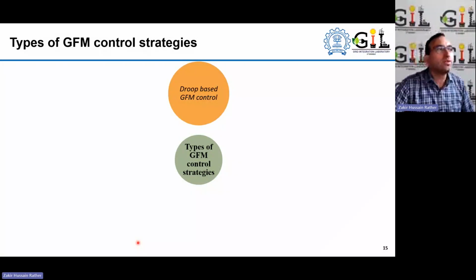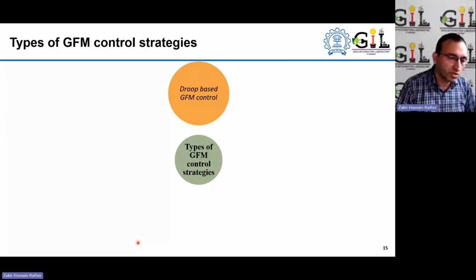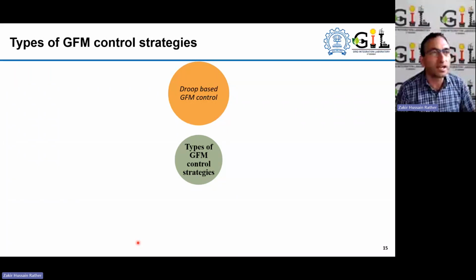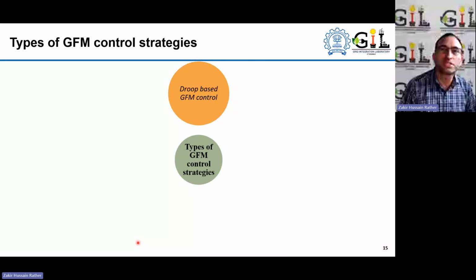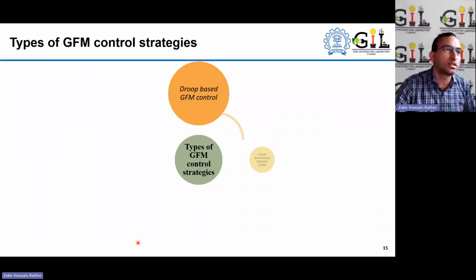Now, if we look closely, the difference is predominantly in the control, the way we control the converter. The hardware broadly remains the same, not identical. There are changes in terms of the current capability of the converters and other storage requirements and all that, but it's predominantly around the control strategies, control philosophies that we apply to this converter technology to make it grid forming.